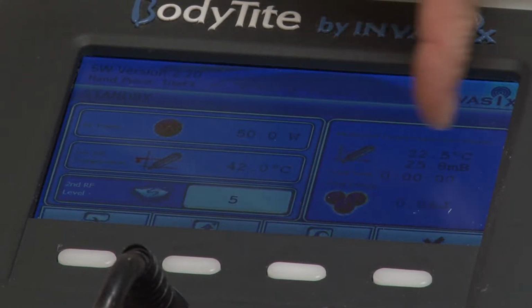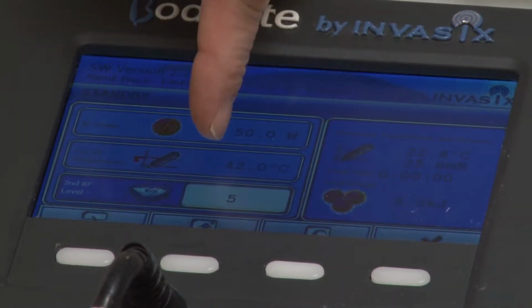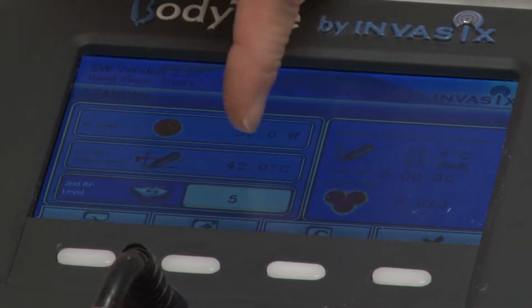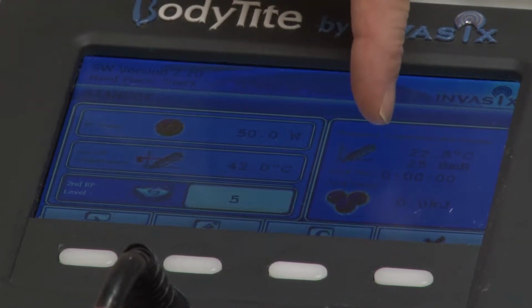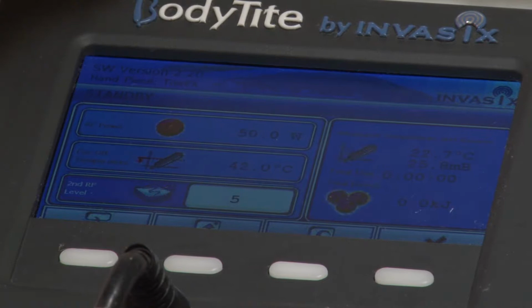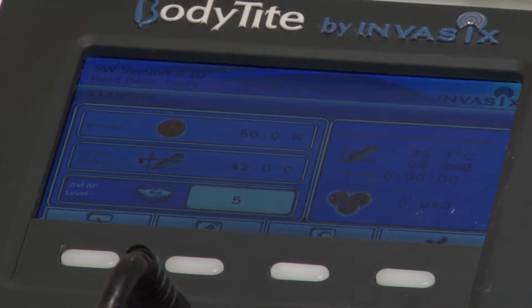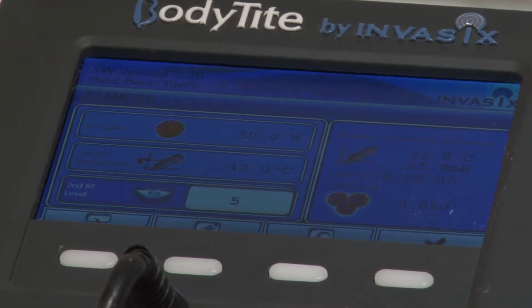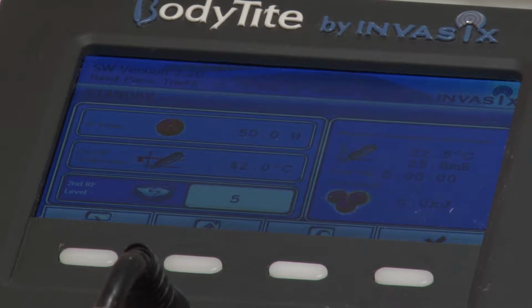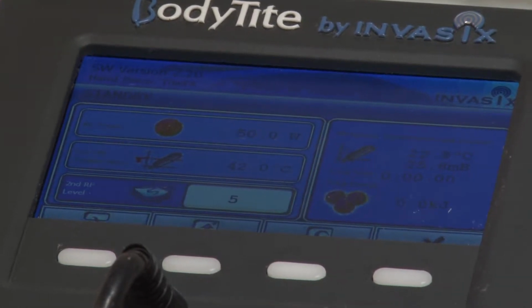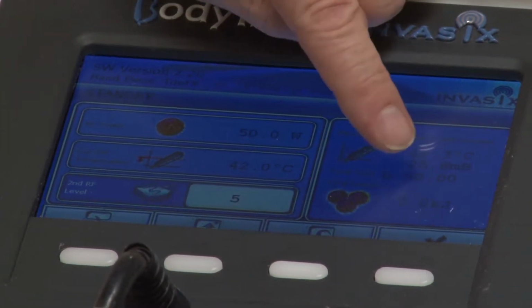And again, we can see the real-time temperature and the desired temperature. When it gets to that desired temperature with the real-time temperature, it cuts off the basic RF and you get high voltage pulsing. When the temperature drops to 0.1 degrees Celsius below that, it will start giving basic RF to heat up that tissue to endpoint again. It samples epidermal temperature about 10 times every millisecond. It also keeps track of the total treatment time.